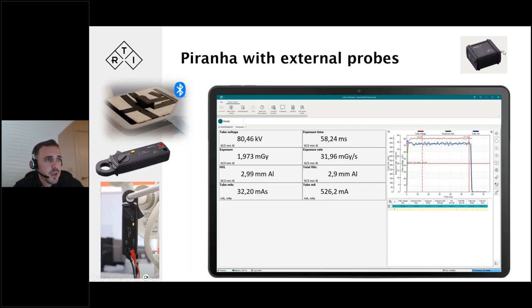You can do that with our mAs One product, which is what we call our invasive probe, where you connect to the mAs socket in the X-ray generator with a couple of cables to measure the tube current in radiography and fluoroscopy. Or you could use our non-invasive mAs Two, as I'm showing here, where you simply clamp it onto the high voltage cable and get a reading.